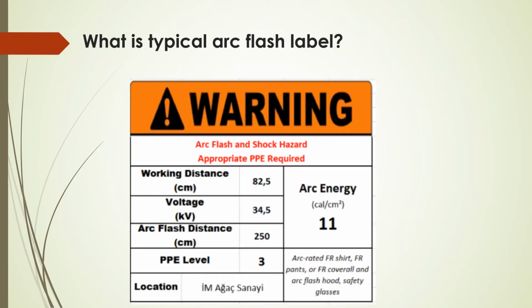What is a typical arc flash label? The figure shows a typical arc flash label, wherein it will give you a warning and say arc flash and shock hazard. It will ask for appropriate PPE requirement. The label will typically describe the arc energy in terms of calorie per centimeter square. Also, it will show you the working distance in centimeter, at what voltage, what is the arc flash distance and what kind of PPEs you are required to wear. Basically, PPEs required for the arc flash hazard mitigation are described as PPE level 1, 2, 3.